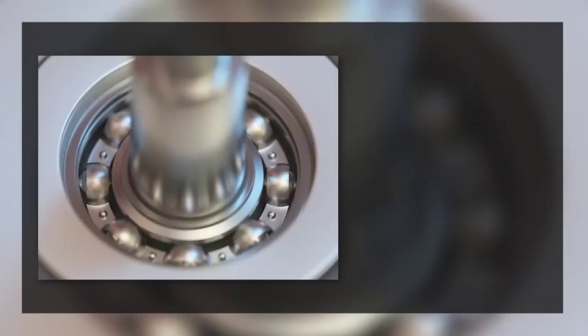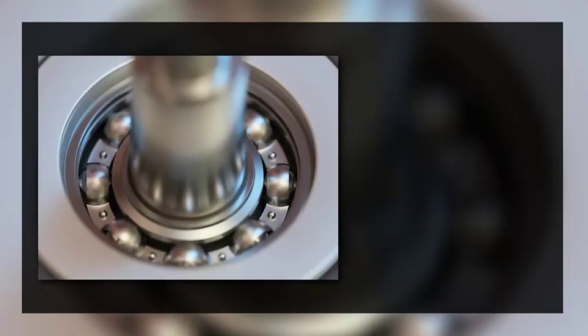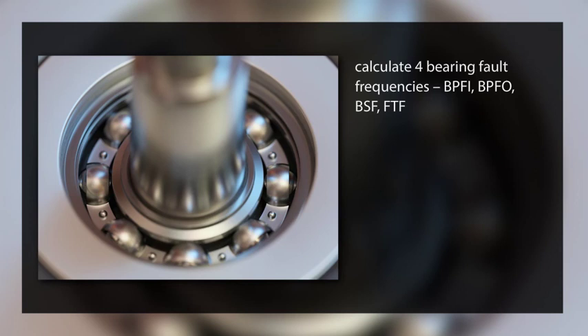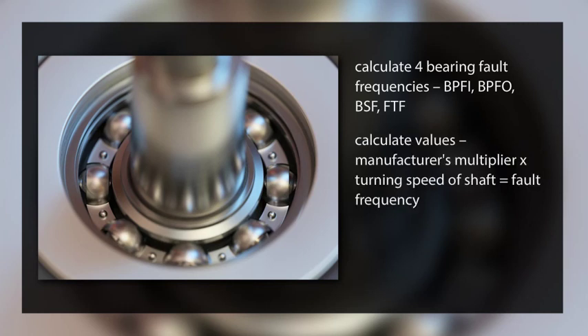Let's summarize. You now know how to calculate four bearing fault frequencies: the ball pass frequency inner race, the ball pass frequency outer race, the ball spin frequency, and the fundamental train frequency. To calculate the values, the manufacturer's multiplier times the turning speed of the shaft equals the fault frequency.